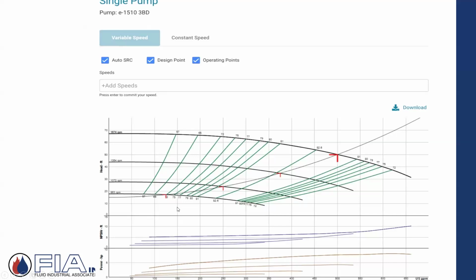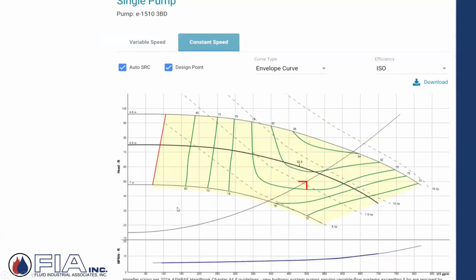And these are just quick examples of picking a pump to meet those conditions. And in that software, I can pick variable speed or I can pick constant speed. So the curves look different. I have a bunch of different RPMs being selected, and what that control curve or system curve looks like, starting at that 20 feet of head, versus that constant speed. Now I'm changing impeller diameter. So if I have to meet a certain design condition, I'm going to pick a certain impeller diameter.